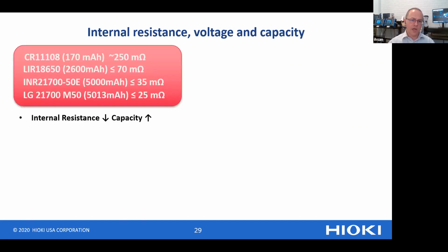Now I'm going to talk a little bit about the internal resistance, voltage, and capacity of lithium-ion cells. Here is some information that I was able to glean off the internet from some data sheets, showing different lithium-ion cells. The top one, for instance, is 170 milliamp hours, and the internal resistance is about 250 milliohms. The one below it is 2,600 milliamp hours, and the internal resistance drops to about 70 milliohms. As we go down further to the last one, it's over 5,000 milliamp hours, and the resistance is less than or equal to 25 milliohms. What we see is that the internal resistance typically drops as the capacity increases. In other words, as the capacity increases, our test current requirement increases.